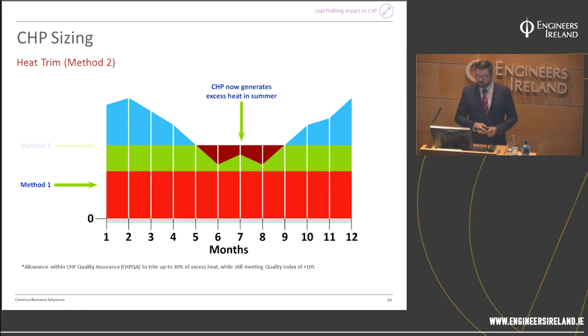Method two is for when there might be a conflict between planning applications and driving carbon savings on a site. People want a larger CHP with a larger thermal output, so instead of being risk averse like in method one, people tend to design a larger CHP to maximize the on-site value, which is understandable. But the problem occurs in the summertime when all the heat is not utilized.